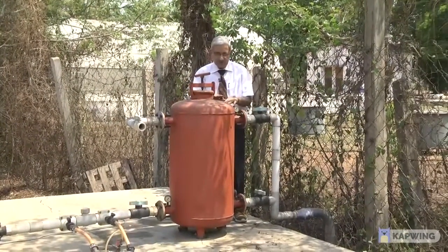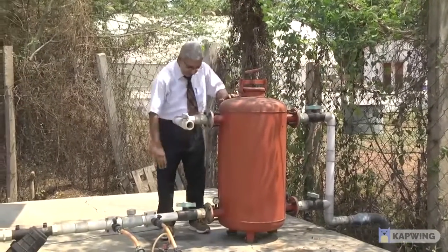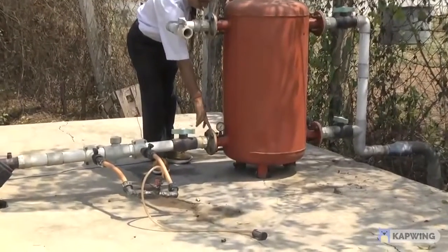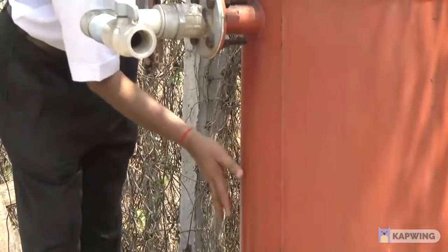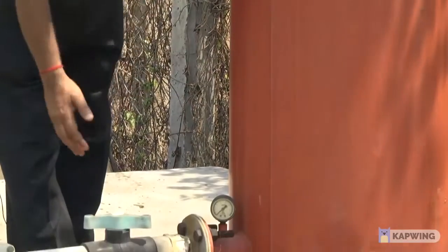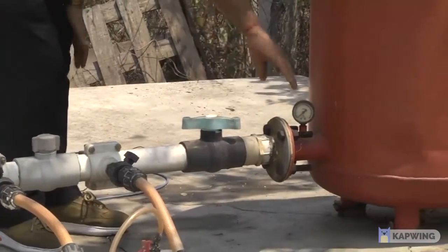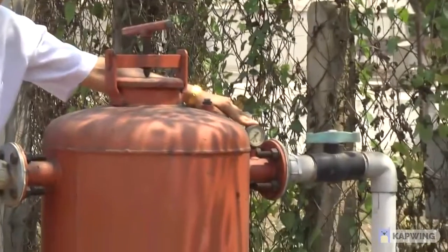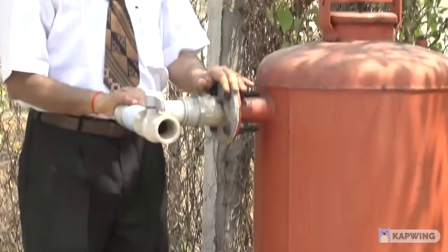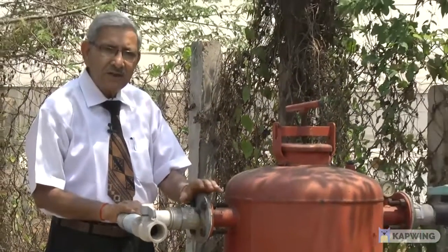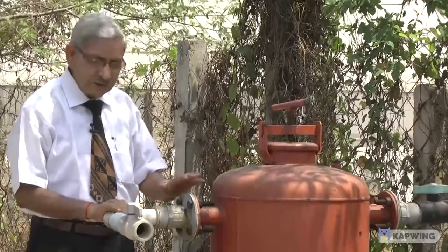Water passes through this filter, goes through the layers, and at the downstream end you can see the outlet end of the sand filter. Filtered water then enters the system. One inlet end and this outlet end each have a pressure gauge attached. The difference in the pressure head tells how much pressure difference has been caused, and whether the sand is blocked by the impurities available in the water.